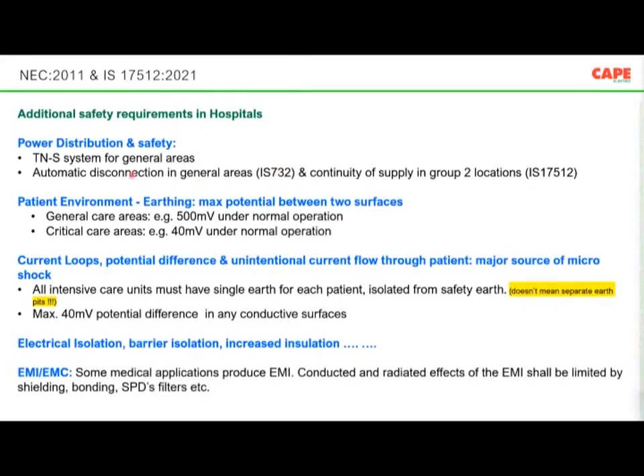And for the medical location, as I said, additional safety features are required, such as a TNS system being mandatory. That means the person doing the work should understand what TNS is, and should check and find out the integrity of the TNS system. Automatic disconnections are necessary. Then there are special requirements for group 2 locations. Then the touch voltage under normal conditions needs to be tested. Then the current loops. For example, once you operate some equipment which creates a kind of leakage current, or sometimes some electromagnetic influences, parallel paths may also have a current flow which can create problems. So all these things must be tested.